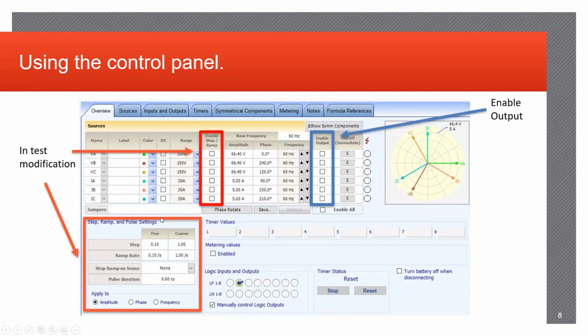Another couple sections here, this step ramp and pulse settings section is extremely useful for manipulating current or voltage values while the test set is actually running and injecting. So this can be utilized when you start up the test set and begin injecting values into the relay. You can actually set parameters for a step or ramp to be placed, and you can manipulate that while the test set is actually live and change the values in real time, which is extremely useful, especially when you're testing multiple different points and different values. You don't have to keep shutting off the test set and turning back on, et cetera. You can just change them here. And you can change not only the amplitude, but you can change the phase angle during testing, as well as the frequency.